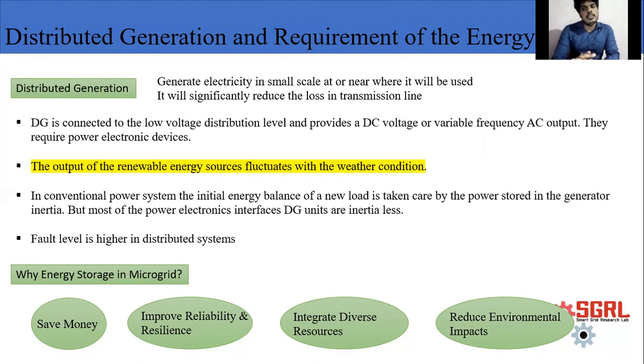If demand suddenly increases beyond supply, that surplus demand can be withstood by generators in a conventional system, because each generator has reserve capacity we can use to fulfill requirements. But with distributed generation, we don't have generators, we have power electronic interfaces, and they don't have that much reserve capacity. So if demand suddenly increases beyond supply, we cannot do anything.